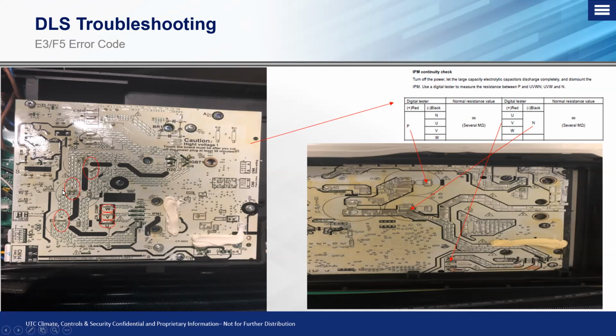Once you've confirmed that the capacitors are good, take that same red lead, put it on the positive post, and then go to your U, V, and W terminals. Now you see there's two separate sets right here. You'll see a fan DC, which indicates you have the DC model fan motor, and you have your U, V, and W for your compressor. So you want to verify that you're measuring the correct area, whether you're dealing with a compressor or an outdoor fan motor. Now in this case, we're dealing with a fan motor.